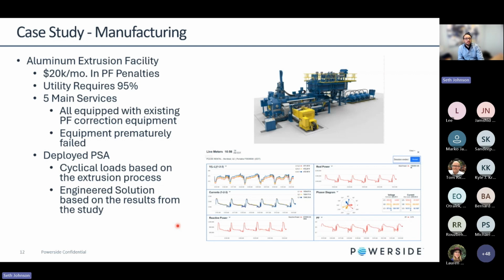This particular customer has a requirement of 95%, which is certainly on the high side. We see anywhere between 85 to 95%. If you're primary metered, or metered on a medium voltage side, sometimes utilities will require up to 98%. And if you are KVA billed, then you're paying for anything that is not at unity, or 100% power factor.